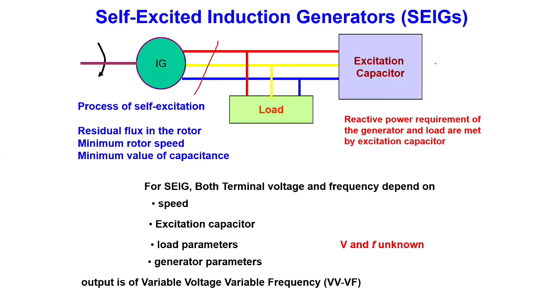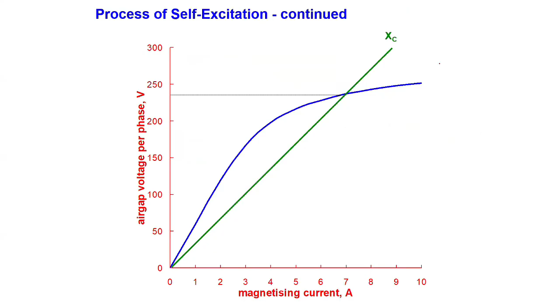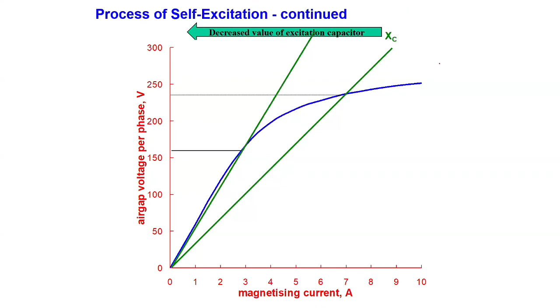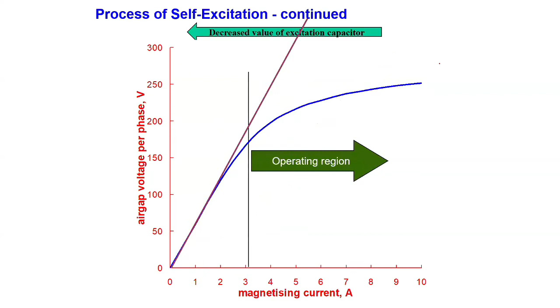The output is a variable voltage and a variable frequency. It is not possible to connect it directly to the grid, or directly to sensitive loads where voltage and frequency must be maintained constant. The frequency and voltage are unknown quantities; they depend upon many parameters. So this is the process of self-excitation. Here the characteristics show the air gap voltage versus the magnetizing current. Similar to the DC shunt generator, instead of a resistance line, here we have a reactance line, XC. When you decrease the value of the capacitor, the line shifts like this. We can observe that this is the operating region of the self-excited induction generator.